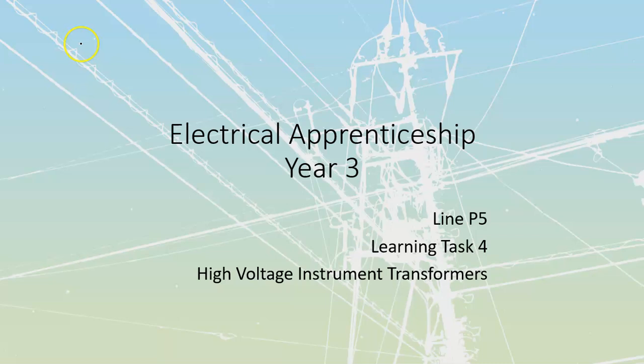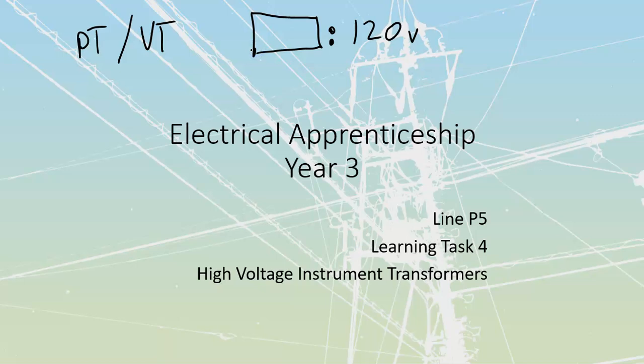One of the things that they're going to have as a standard for my PTs or VTs, depending on which one you want to have, is that my secondary is always going to put out a rated value of 120 volts. Whatever we have in our primary, it could be 14.4 kV, or whatever it's going to be, is going to be rated against a secondary value of 120. We'll just leave this as an open box. We'll just insert whatever our high value is into that one, and it'll be to a ratio of 120.